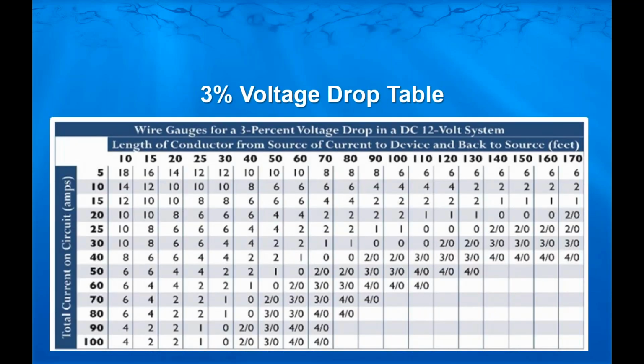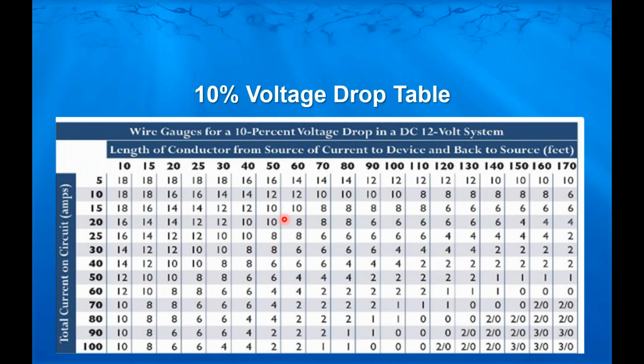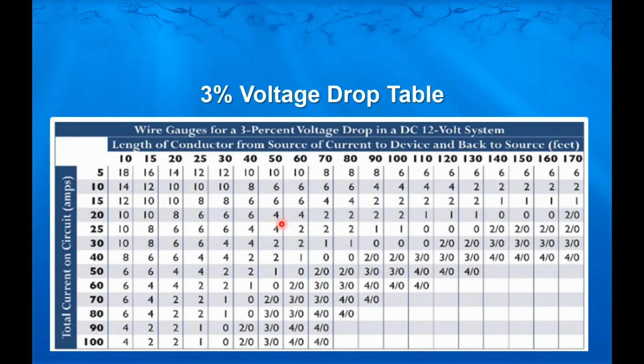The number you land on for proper wire gauge is going to be the proper wire gauge for that circuit. So on our 3% table, let's just deal with 20 amps. Say we've got a 50 foot circuit. That's 25 feet and 25 feet back. For 20 amps on 50 feet for a 3% volt drop, we've got to use a piece of number 4 cable. That's a fairly substantial piece of cable. Compared to our 10% volt drop table, 20 amps, 50 feet, we only need a piece of number 10. So you can see there is quite a sizable difference in wiring between 3% and 10%.